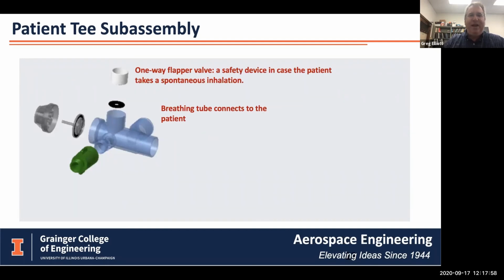There was a one-way flapper valve that we designed into the system. This was so that if the patient took a breath spontaneously, they would have some gas. If it wasn't the oxygen supply, it was room air that would be supplied, so that they didn't have a restriction in their breathing. There's also a pop-off valve, so that if a mistake was made and too much pressure was put into the system, it would pop off and not harm the patient.